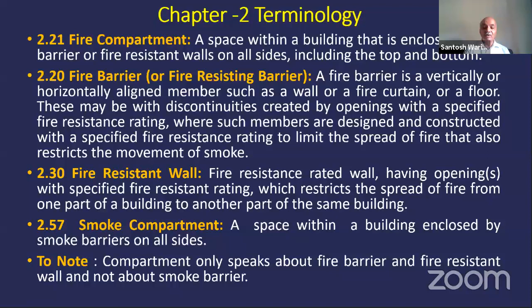Then there is another component involved this time, that is the smoke compartment. This was not there in 2005. That is the space within a building enclosed by smoke barriers on all sides. But there is a note below it that the compartmentation only speaks about the fire barriers and fire resistance and not about the smoke barriers.